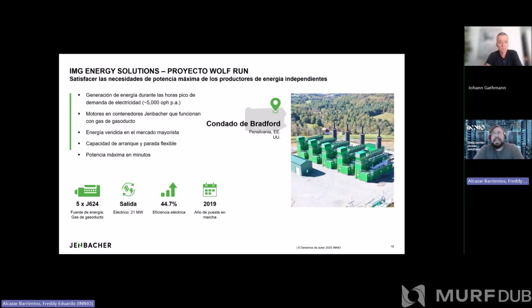Another example is IMG Energy Solutions, also in the United States, in Bradford. Here generation happens mostly during peak hours, around 5,000 hours a year, what we'd call a peaking plant. Depending on the size of the site, you can increase the number of engines depending on the gas supply available at a single location. This plant has 5 J624 engines, providing a total of 21 megawatts at 44.7% efficiency, and has been in operation since 2019. It has very good start and stop capability, quite flexible, since it's used for selling when the price is at its highest or best.